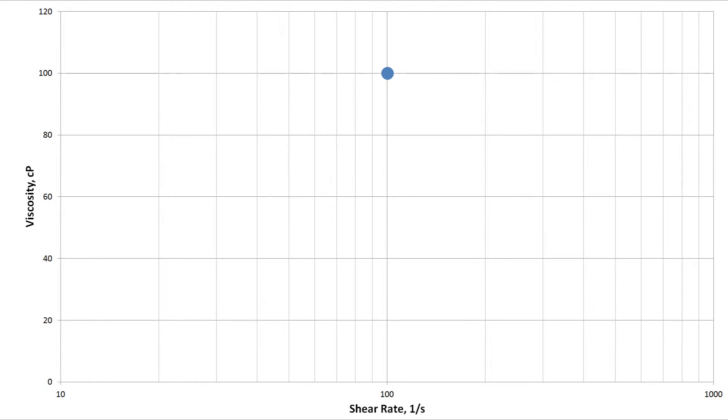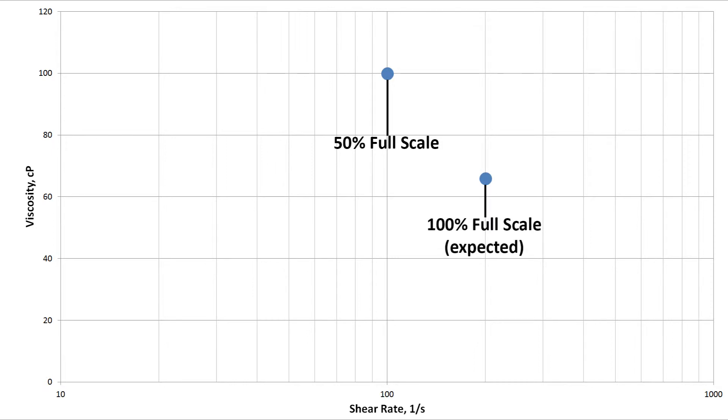For example, let's say you test a 100 centipoise sample at 100 reciprocal seconds that is equivalent to 50% of full scale. You double the shear rate, expecting that to be your maximum 100% full scale, but your viscosity drops down to 66 centipoise.